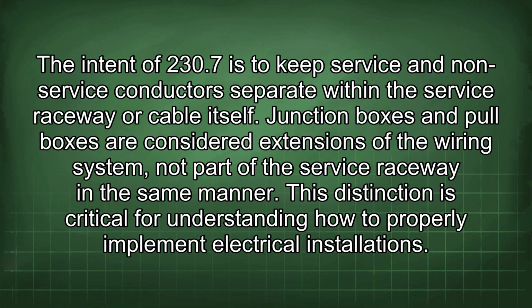The intent of 230.7 is to keep service and non-service conductors separate within the service raceway or cable itself. Junction boxes and pull boxes are considered extensions of the wiring system, not part of the service raceway in the same manner. This distinction is critical for understanding how to properly implement electrical installations.